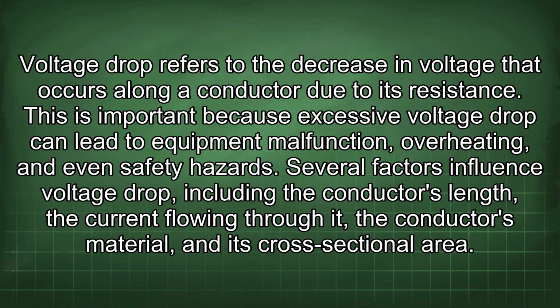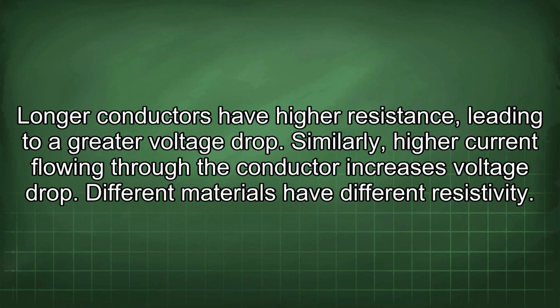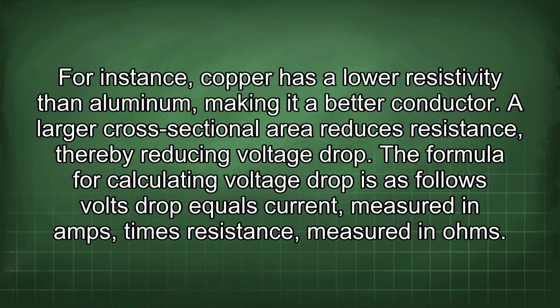Several factors influence voltage drop, including the conductor's length, the current flowing through it, the conductor's material, and its cross-sectional area. Longer conductors have higher resistance, leading to a greater voltage drop. Similarly, higher current flowing through the conductor increases voltage drop. Different materials have different resistivity. For instance, copper has a lower resistivity than aluminum, making it a better conductor. A larger cross-sectional area reduces resistance, thereby reducing voltage drop.